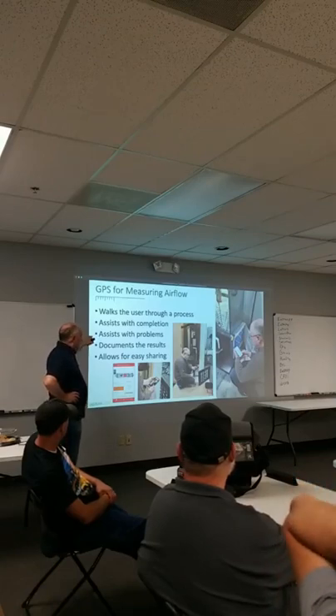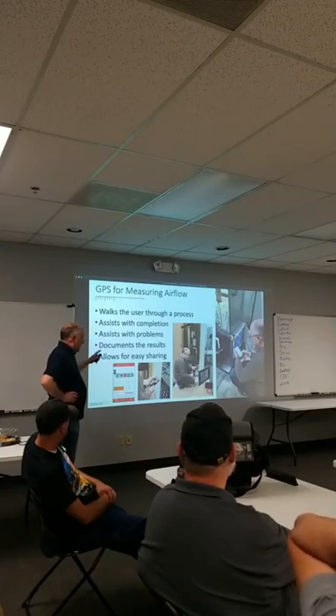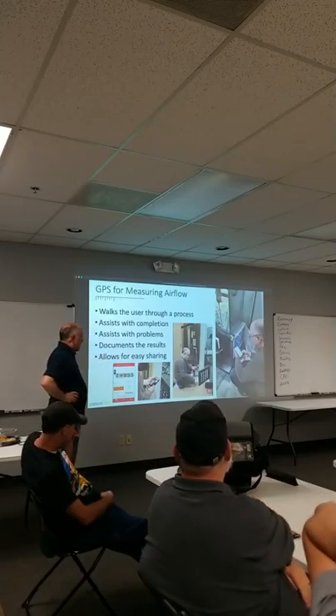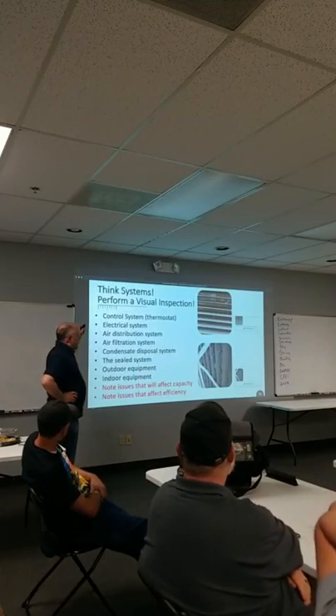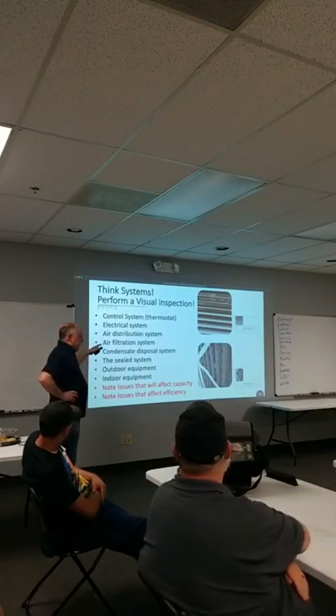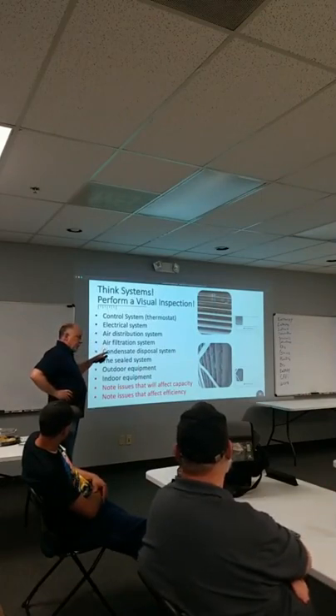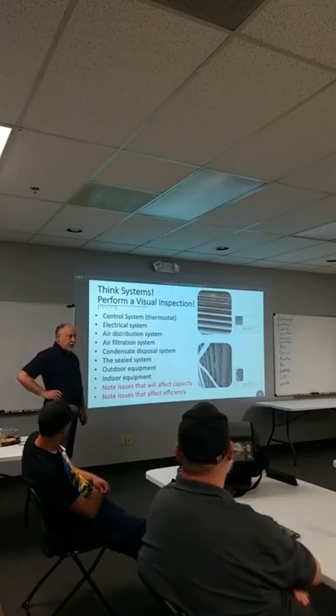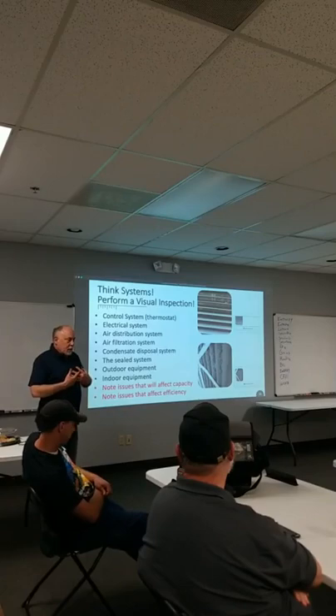Measuring airflow with the TrueFlow grid, we should probably do a separate class on that, but it's probably one of the most accurate ways of measuring airflow in the industry today. There's nothing more important when you're using our software than making sure you're doing a thorough visual inspection. One of the other problems we see out there is guys that go out, deploy all the probes, and overlook some of the most obvious things, right?